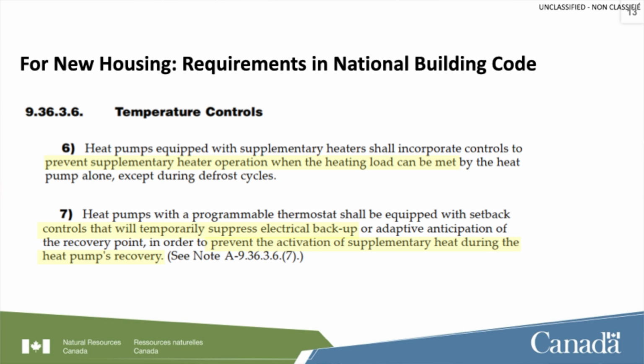So again, I talked a little bit about the code. This is the requirements in the National Building Code. We actually have to put in controls to prevent the supplementary heater operating when the heat load can be met by the heat pump. That's that hybridization version. The heat pumps with a programmable thermostat shall be equipped with a setback control that will temporarily suppress the electrical backup or adaptive anticipation in order to prevent the activation. So this comes in and says, even if it can't meet it, we still have to give it a chance. These are the two restrictions that we have within the building code.